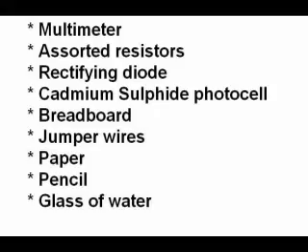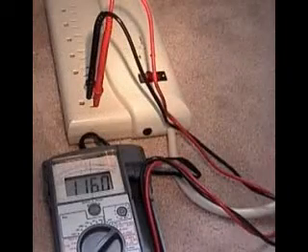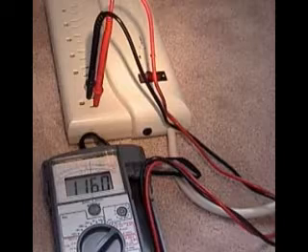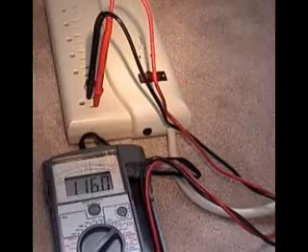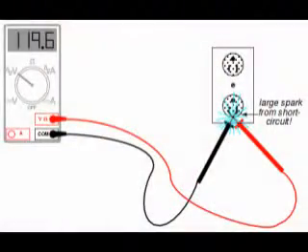However, be sure to never measure the resistance of any electrically live object or circuit. In other words, do not attempt to measure the resistance of a battery or any other source of substantial voltage using a multimeter set to the resistance or ohms function. Failing to heed this warning will likely result in meter damage or even personal injury.